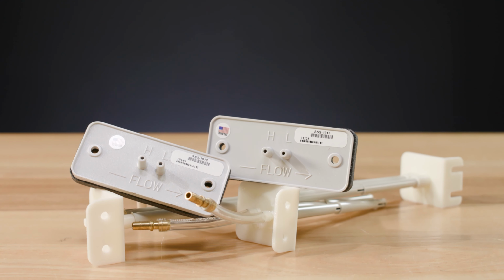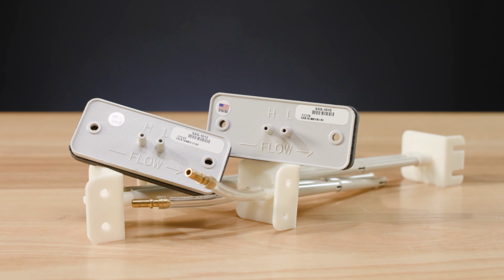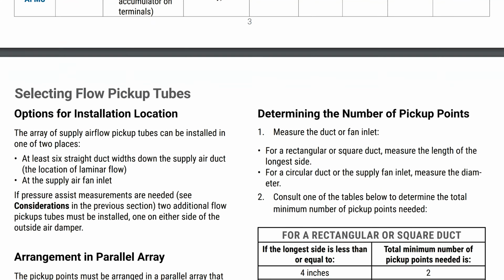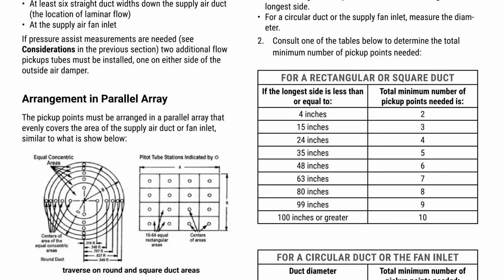Before starting the installation, there are a few recommendations that need to be mentioned. The first recommendation is to confirm that you have enough pickup tubes to be installed for the size of the opening to get an accurate average value for the airstream. Multiple pickup tubes, at least 2 of them, are recommended in a parallel pitot tube array. More averaging points, meaning either more or longer pitots, are recommended for larger duct dimensions. Please reference the chart in the selection guide for more information.